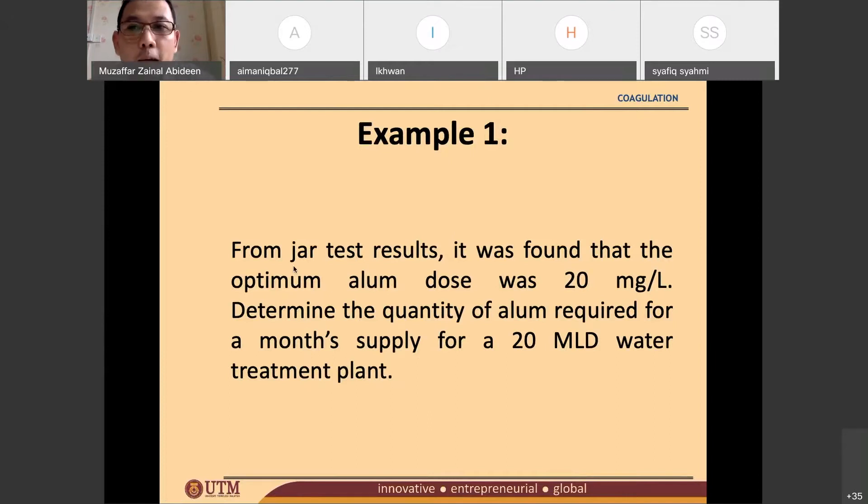From jar test results, it was found that the optimum alum dose was 20 mg per liter. So they have different beakers and somehow the beaker that they add 20 mg per liter give the optimum results. Determine the quantity of alum required for a month's supply for a 20 MLD water treatment plant. So they would like to see or to determine the quantity of alum in a month, and the water treatment plant has a 20 MLD flowrate.